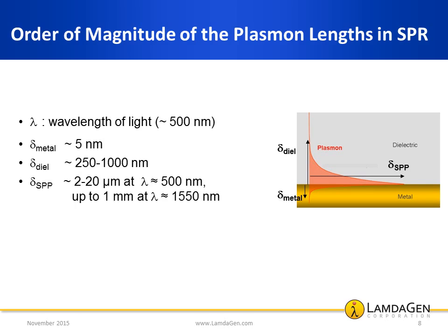Assuming we use an excitation light with a wavelength around 500 nanometers, let's examine the characteristics of the resulting plasmon lengths in SPR using a planar gold surface. The plasmon field in the metal is on the order of a few nanometers, meaning the surface plasmon does not penetrate deep into the metal. Conversely, the evanescent field in the dielectric can extend from 250 nanometers up to a micron, meaning the surface plasmon can sense up to a micron away from the surface. Finally, the surface plasmon propagation length can extend a few microns up to the millimeter scale in very ideal situations.